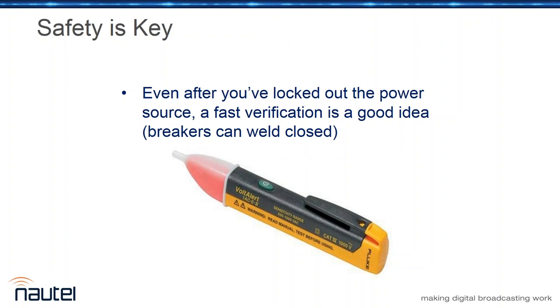Breakers will occasionally, circuit breakers will weld closed. You may have a piece of equipment with multiple power entrances. Some of our old 50 kilowatt AMs had two high voltage, two 480 volt entrances for the power supplies, and then another 120 volt entrance for the exciter. So sometimes just shutting the breaker off may not be enough. You may have more than one breaker to switch off, and testing things before you touch them is always a really, really good idea.